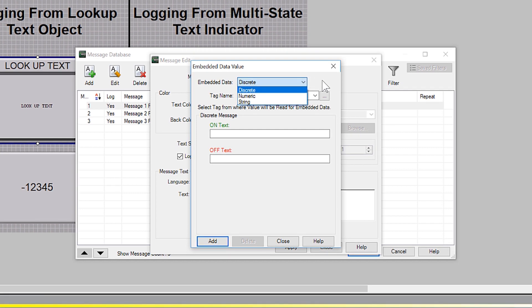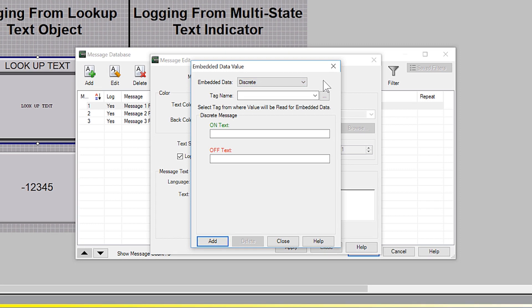When using a numeric or string tag in the message, the value of those tags will be embedded into the message. The discretes will trigger a different static text message based upon the on or off state of the discrete.